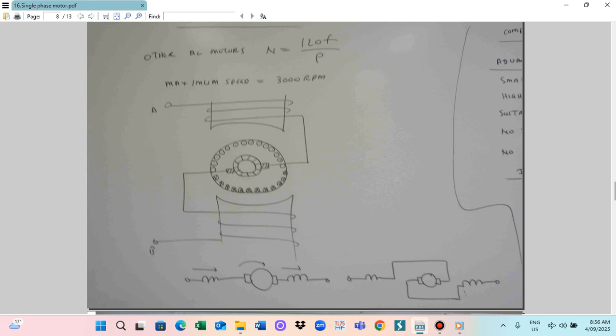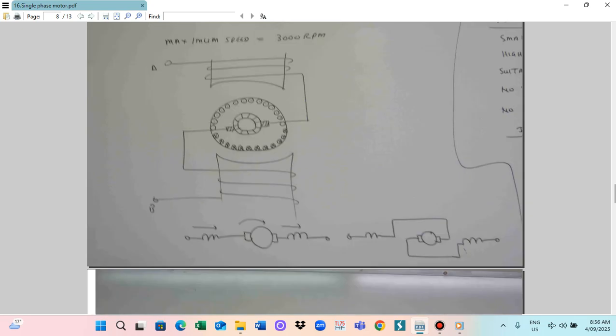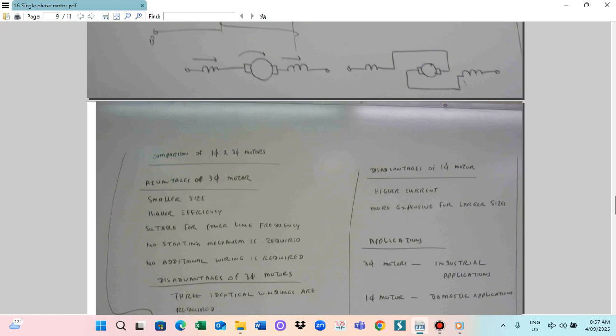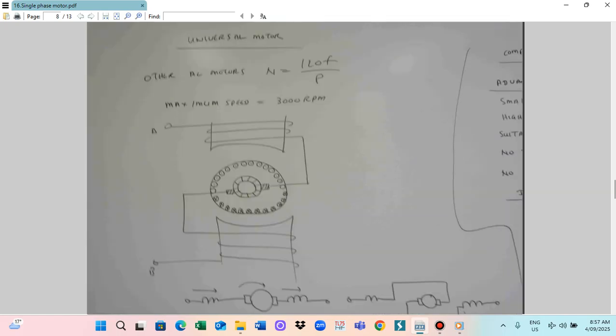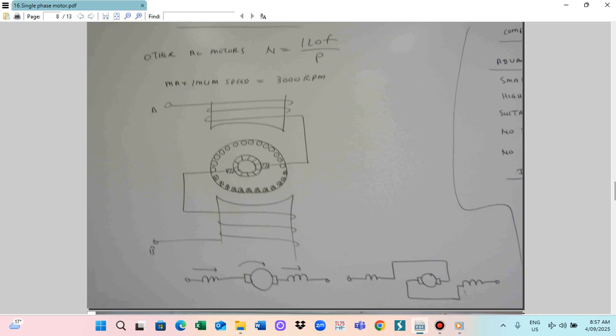The first one is the universal series motor. The universal series motor can get the highest speed. 10,000 RPM or 20,000 RPM can be provided because this motor is like a DC motor. Therefore, drilling needs a very high speed, so for those drill machines we usually use the universal series motor. This is the connection diagram of the universal series motor.